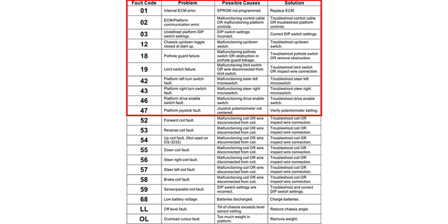These are among the most common faults seen on these machines as they are often caused by the operator when not operating the machine correctly. For safety reasons, the ECU faults if one of the buttons is closed or the joystick is out of neutral when the control system is powered on. This is to ensure that there is no unintended movement of the machine if a button or the joystick is damaged or stuck. Be aware that the ECU performs a self-test when it is powered on.